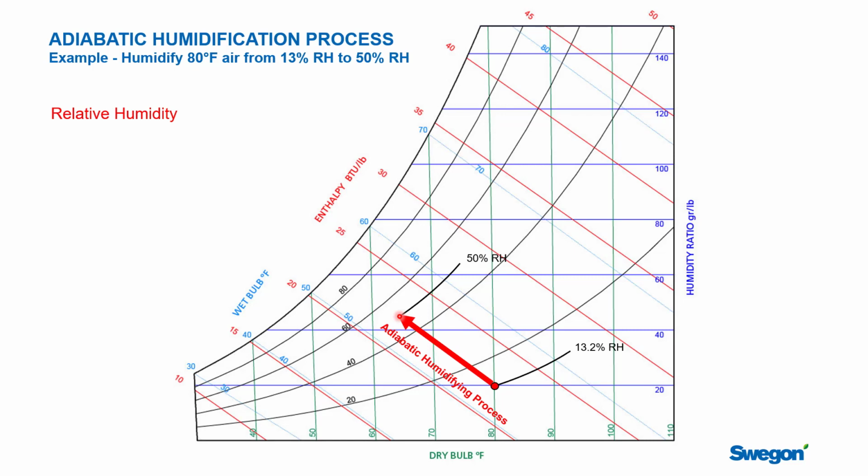If you want an example, think of a residential pad type humidifier on a furnace. Some of the return air is run across a pad that's wet. That air is coming back from the house, so it's relatively warm. The air goes across the pad, and the sensible energy of the air is being used to boil the water.